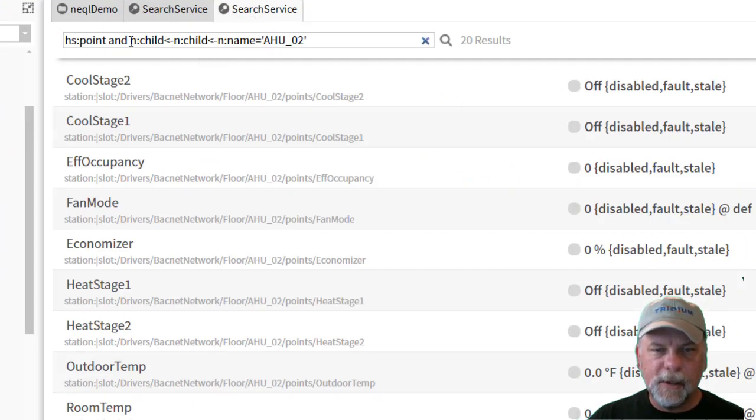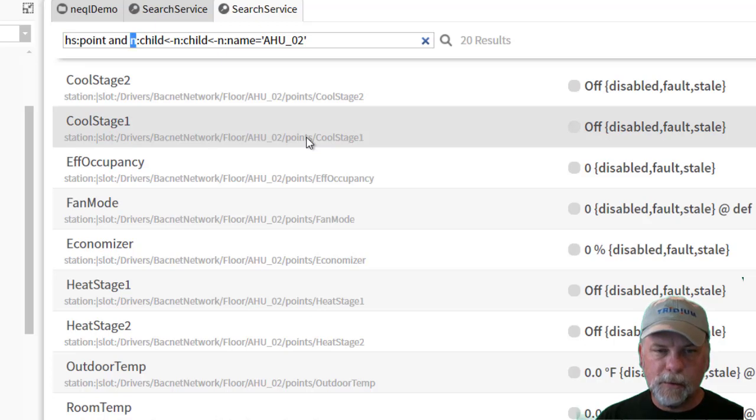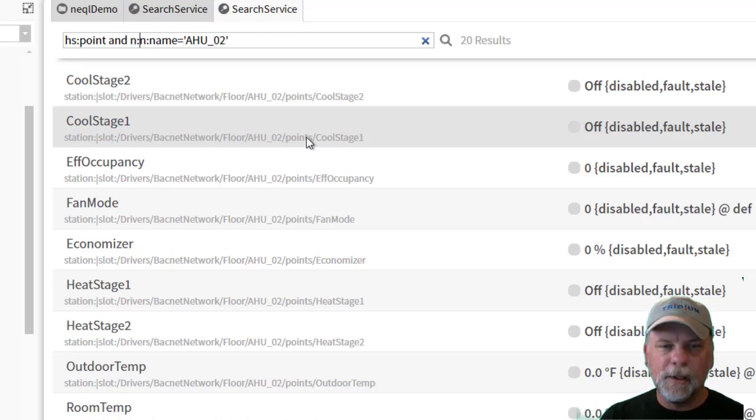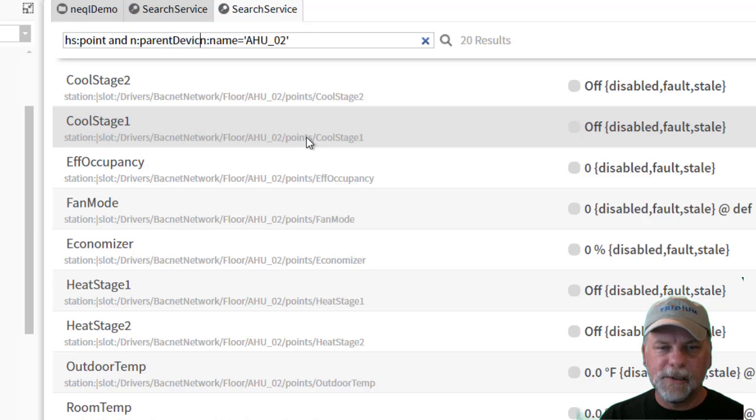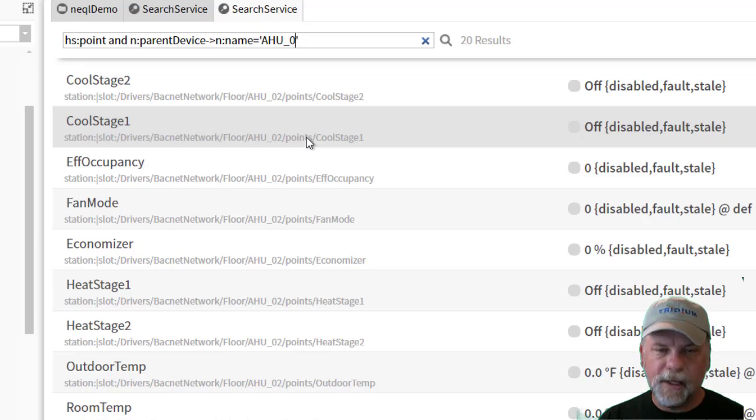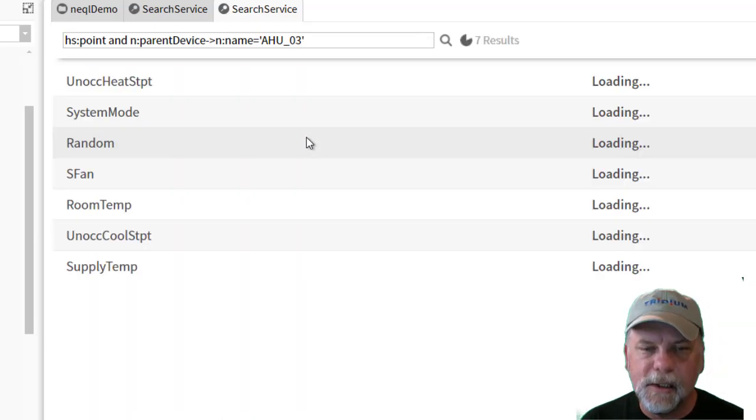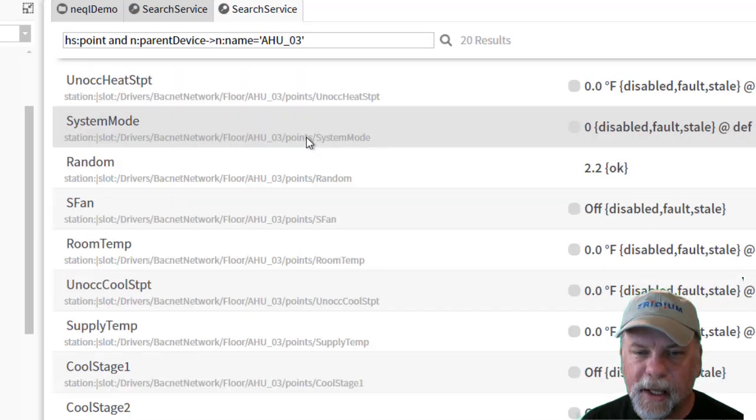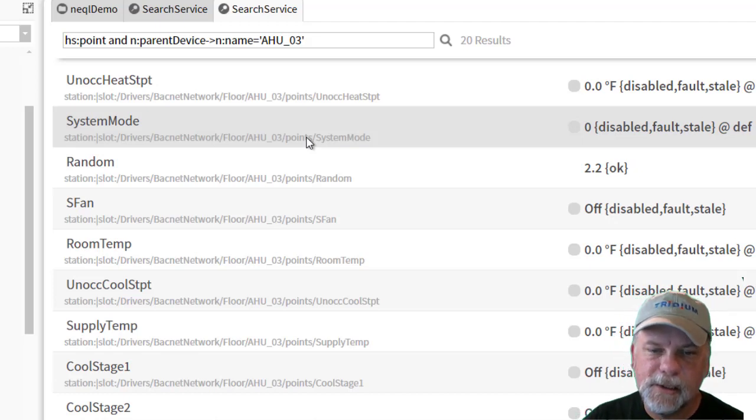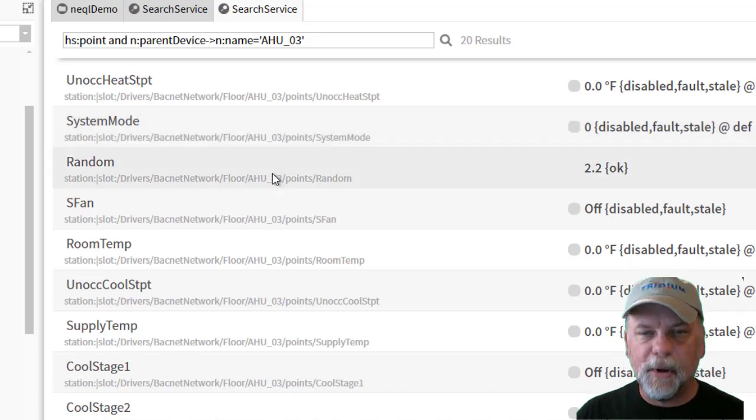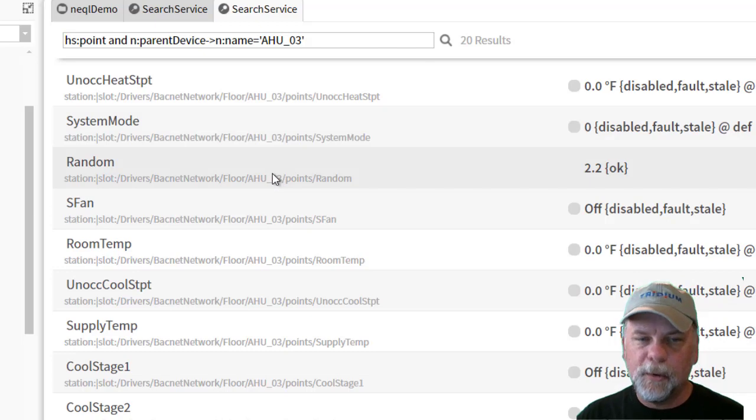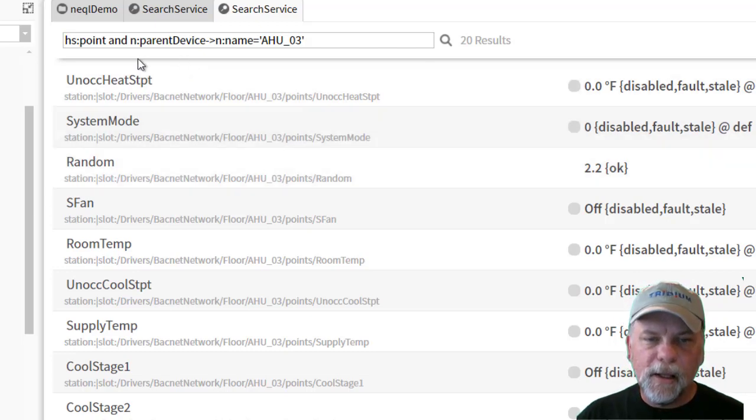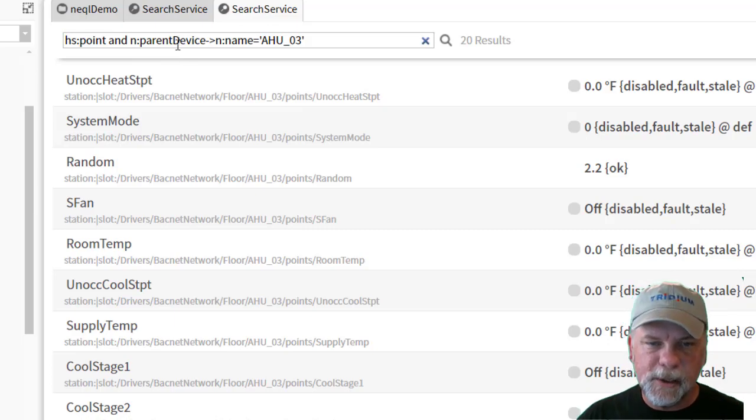So instead of maybe using these multiple relations here, what I could use is the n colon parent device relation, just a single outbound relation, and then check the air handler device to see which points are related to that specific device. And so you can see again air handler three is what's showing up in the slot path here on all these points, and it's simpler, a single traversal, one relation instead of multiple relations being traversed there.